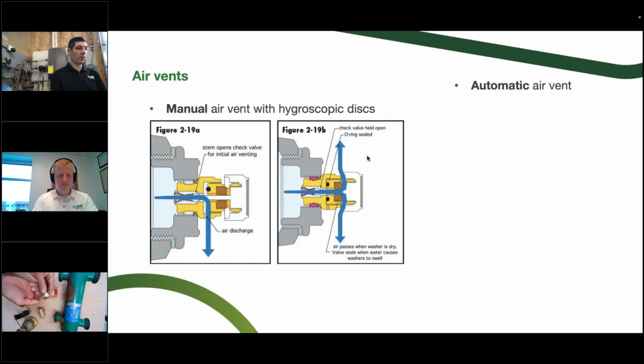So then let's say another bubble of air finds its way into that radiator later, the air can come out, but as soon as it senses some water, those little gaskets, those washers, will swell when they get wet. So it can be in automatic mode. As soon as it has water present, it's going to close, so then it's not going to drip. And then when it dries out again, it'll continue to purge air. So that's an automatic setting for a really simple device that has a little bit more complicated path on the inside there, instead of just a bleeder valve that you would have in the front of a pump or something simple like that.